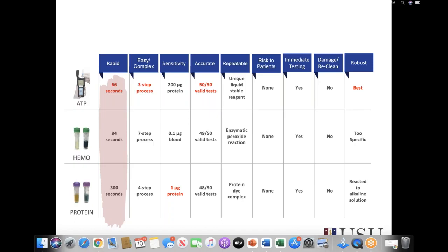Now, the way that I measure the timing of testing was from the time I selected the instrument to the time I recorded the results. So that includes picking the instrument, measuring with the gauge, selecting the brush, setting up the kit for testing, placing it on the unit, and then allowing the unit to do the analysis and then record. In the case of ATP, I didn't have to record them on paper because the unit provides for electronic storage of those results, so I didn't have to go to that step. So that's how the ATP time measuring went. It only takes 15 seconds to get the results, but the whole process took 66 seconds.